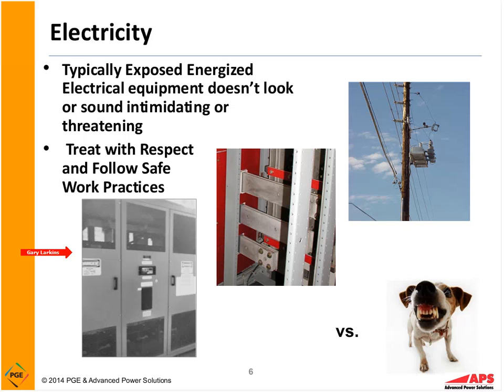But we've had sites before where there's been, whether it be a rat or contamination inside the gear or a defect, where there's been an electrical explosion, and that electrical explosion actually came out through the vent holes. In one case in particular, nobody was burned, fortunately, because people were down at the other end of the room. But there have been cases where people have been burned. The key thing here is to always treat it with respect and follow safe work practices, whether we're opening up gear or whether we're around electrical gear.